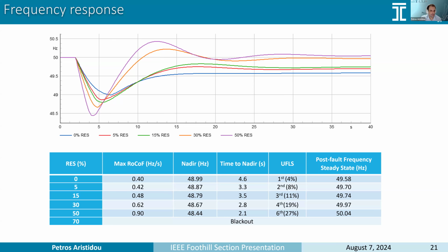Indeed, the plan is to go not to 100%, but as close as possible. So the dream is to go to 100%, of course, like everybody's dreaming about that. However, it's not possible to remove synchronous generators altogether because it's mainly PV and it's a geographically very small area. So if there is a cloud, it will cover half the island, so then you lose half of your generation. So it's not possible to go all the way.